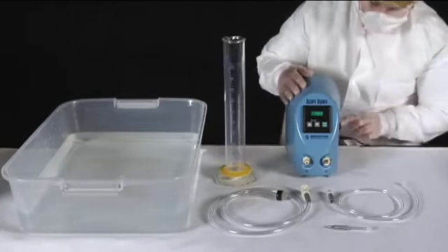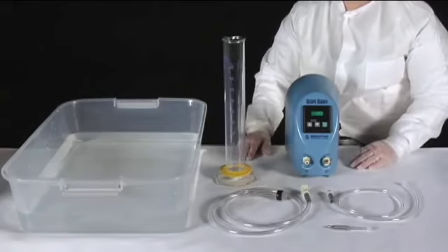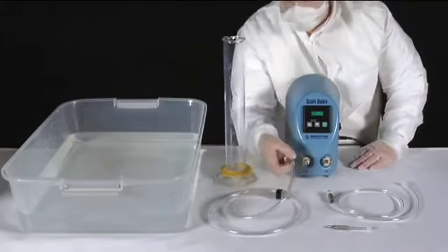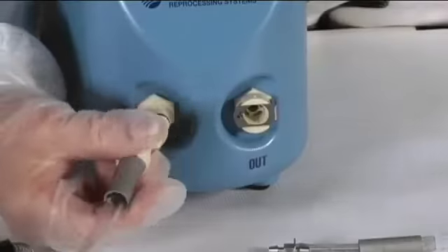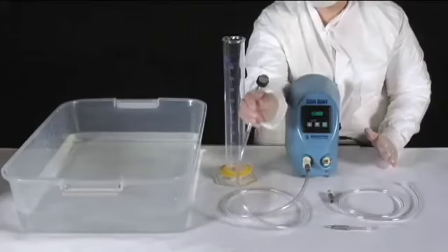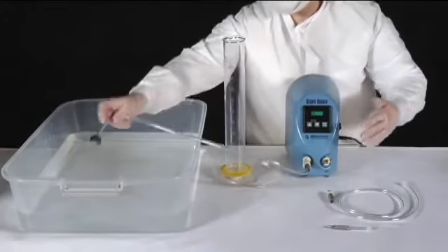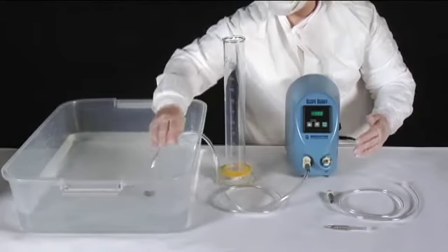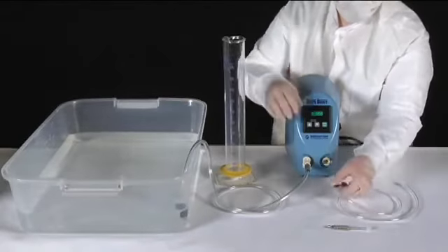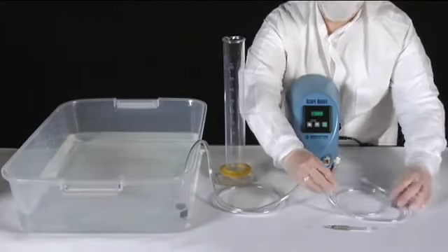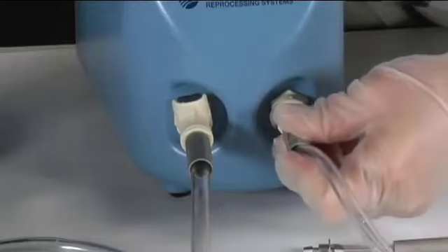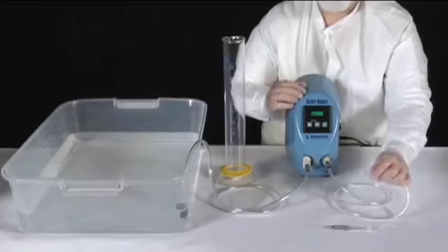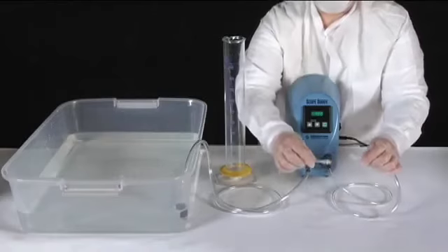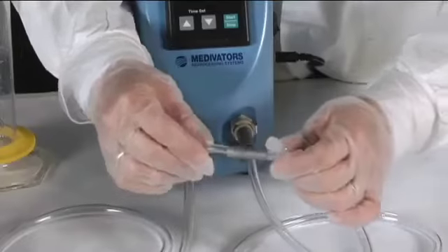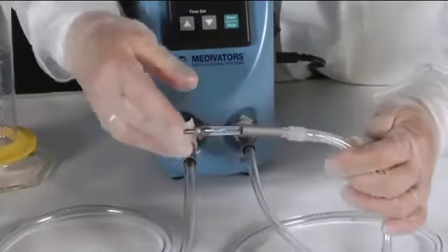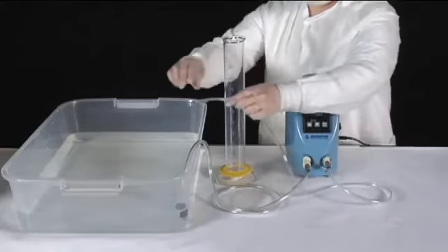Turn unit on by pressing the power switch. Snap the connector of the fluid intake line to the connection port labeled in and fully submerge the screened end in a sink or basin of clean water. Snap the connector of the Universal Cleaning Adapter extension line to the connection port labeled out. Attach the plastic luer lock of the flow verification tube to the remaining end of the Universal Cleaning Adapter extension line. Place the open end of the flow verification tube into the sink.